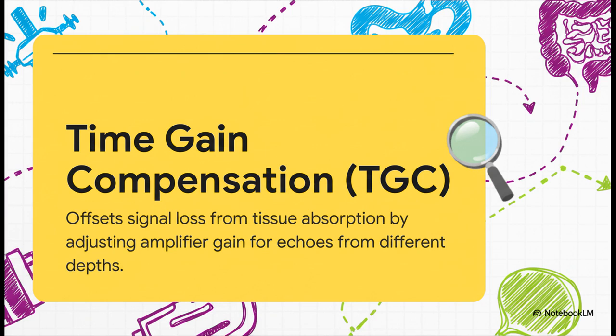Now, as sound travels deeper into the body, it naturally gets weaker and weaker. That means echoes from deep down are much quieter than echoes from right near the surface. That's where time gain compensation, or TGC, comes in. It's basically a really smart volume knob. It automatically cranks up the amplification for those deeper, quieter echoes, making sure the final picture has a nice, even brightness from top to bottom.